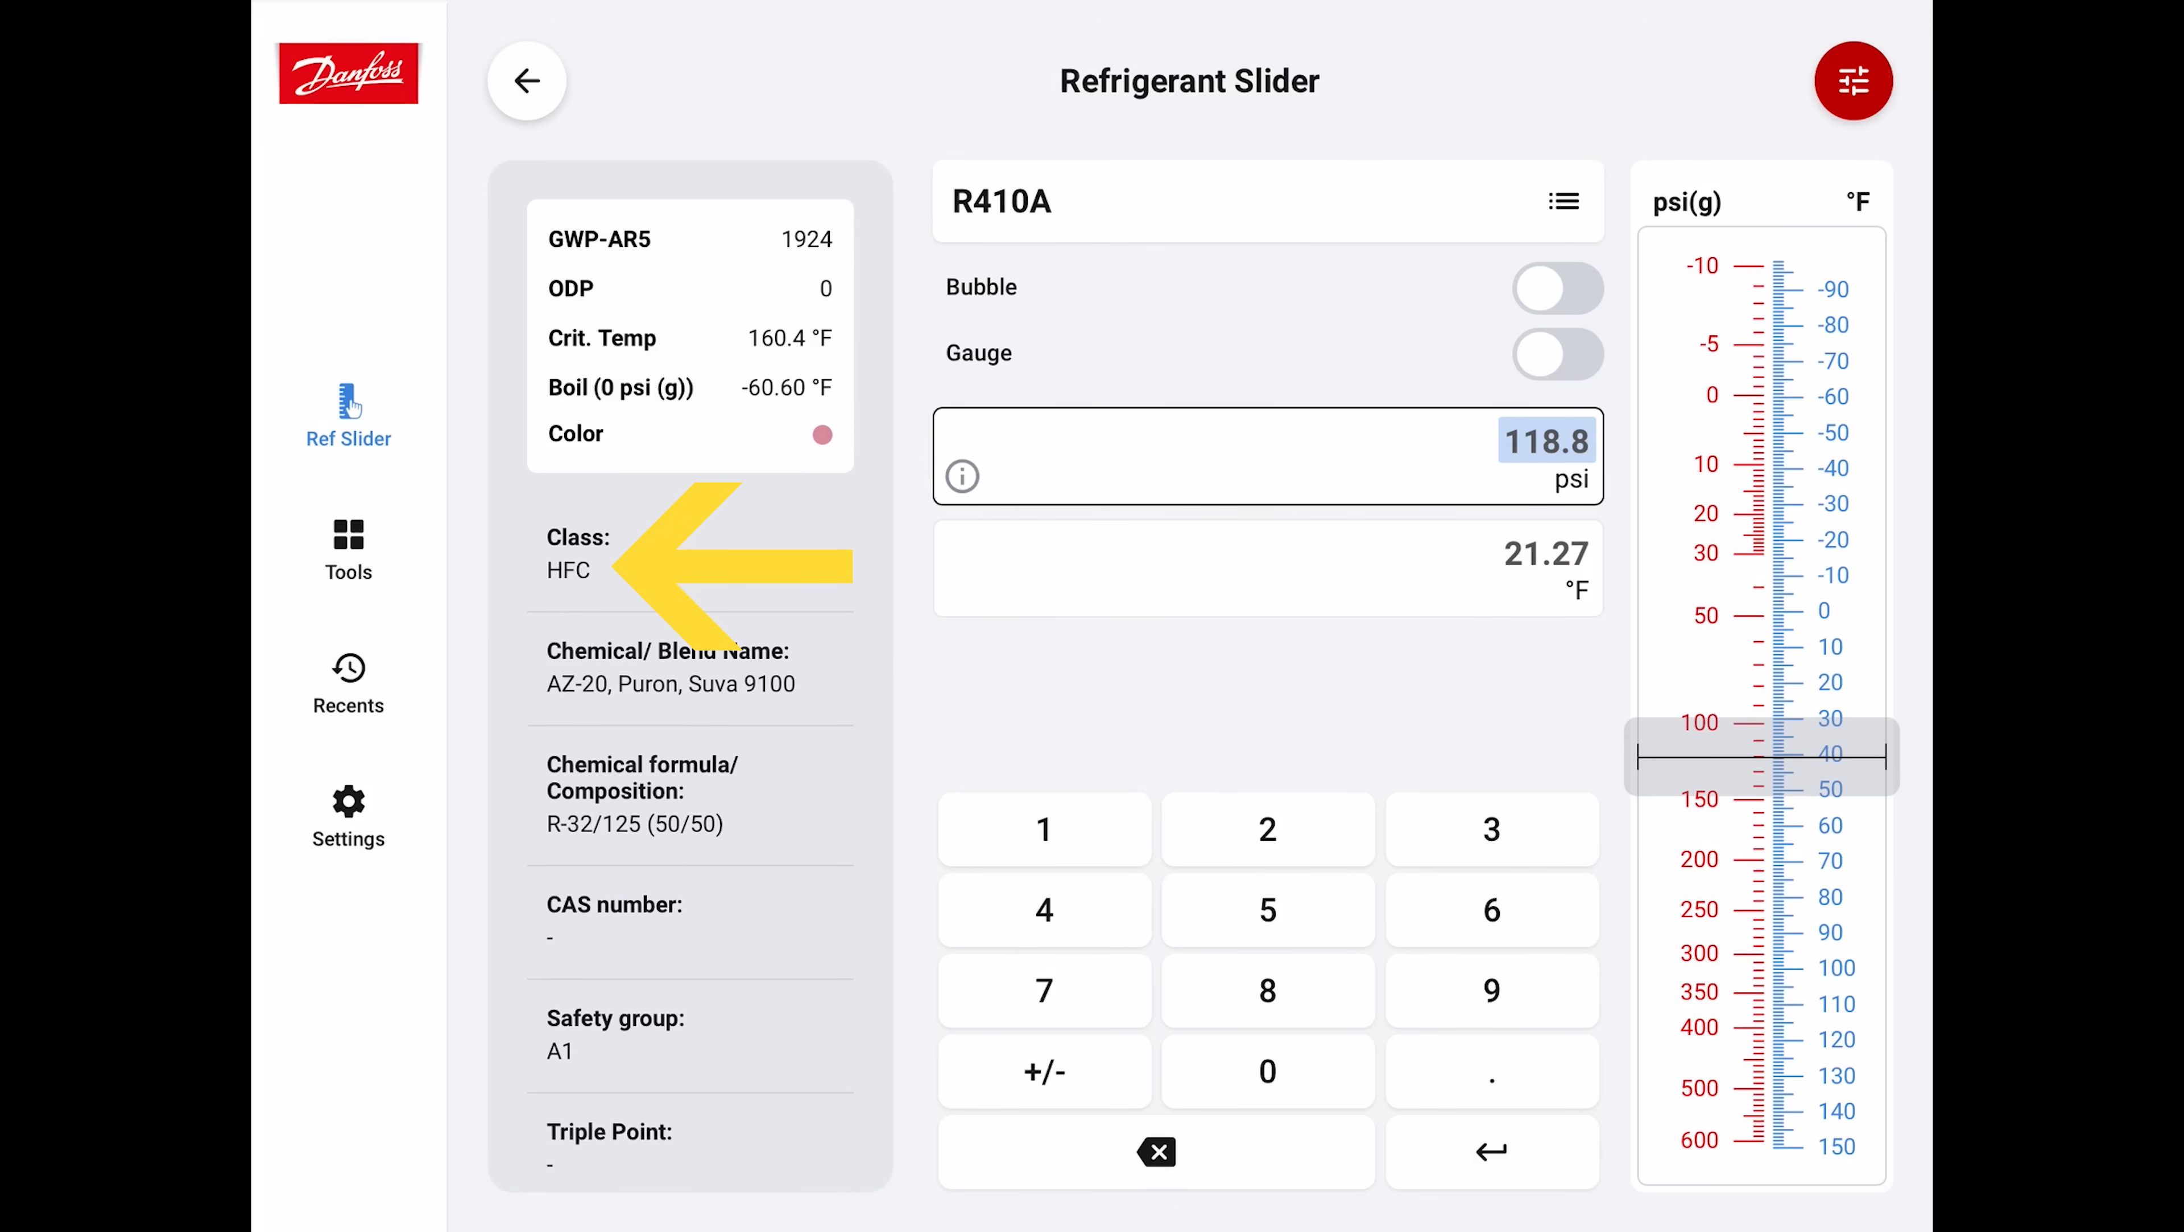You can see that the class of refrigerants is HFC, so it's a hydrofluorocarbon. It's not like R22, which is an HCFC - hydrogen, chlorine, fluorine, carbon. The safety group is A1, so it's at the lowest possible amount of toxicity and flammability.